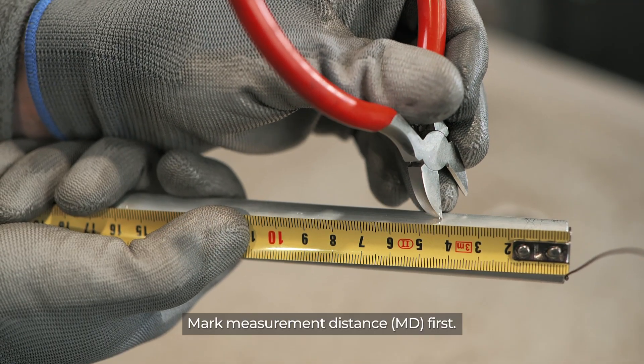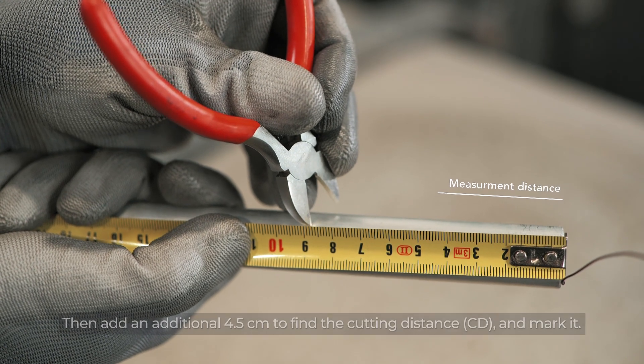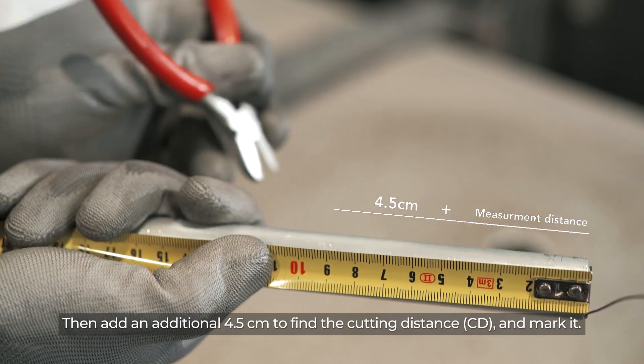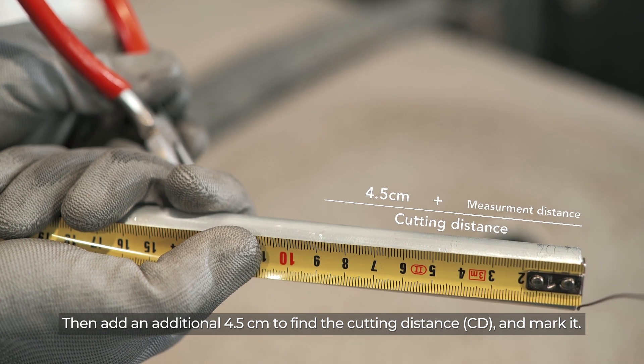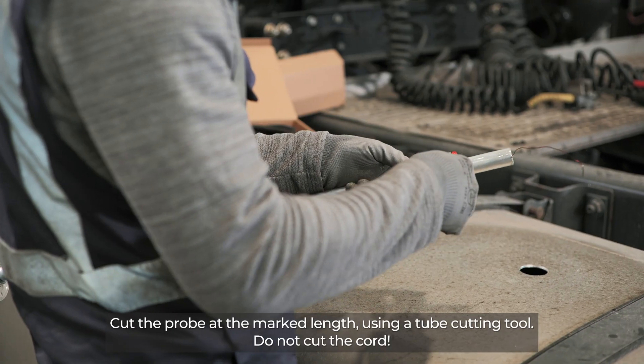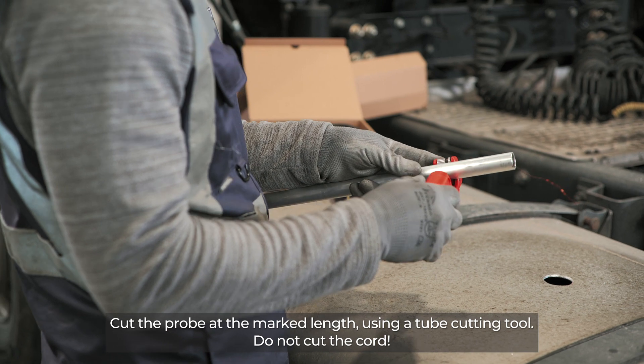Mark the measurement distance first. Then add an additional 4.5 cm to find the cutting distance and mark it. Cut the probe at the marked length using a tube cutting tool. Do not cut the cord.